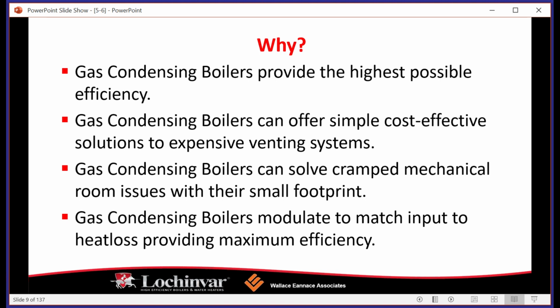Gas condensing boilers, particularly the Lochinvar line, are typically much smaller than an average, again, atmospheric cast iron heat exchanger. This can be good, and as a former installer, this can also be kind of bad sometimes, because you can shoehorn these boilers into very small spaces. So if you're a service tech, sometimes you may walk into a room and kind of scratch your head. But again, these offer solutions.